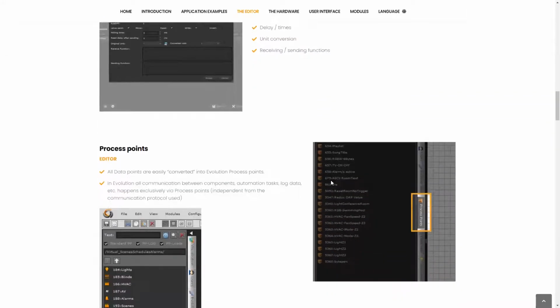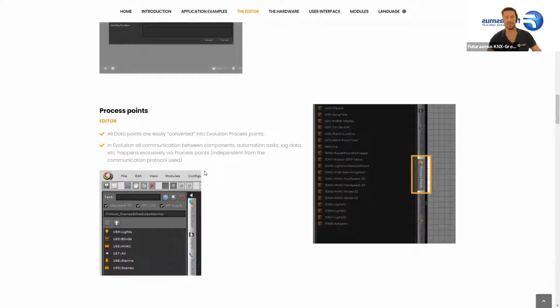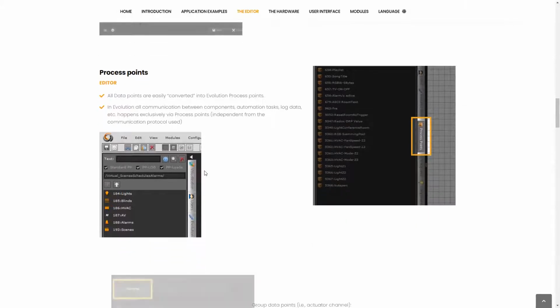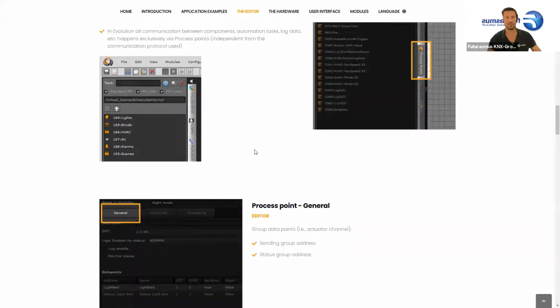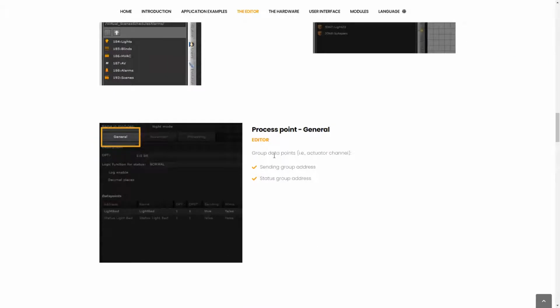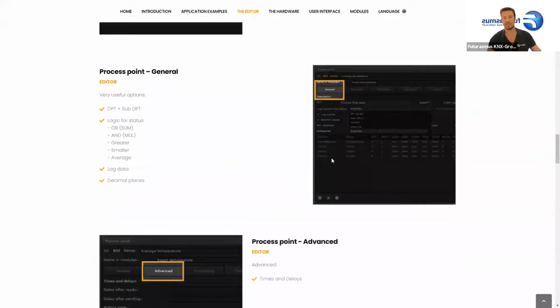You can also set things up in the process point. There are two levels: the data point level and the process point level. In the process point, which can be done very easily, you set up whether it must be stored in the database or not. You can set up the sending group, the sending data points, and the status data points, and the logical function for these status data points. For instance, if you want to display the window contact status of the whole building, you select all the status data points of all the window contacts, add them here, and set up a logical OR - that's it.